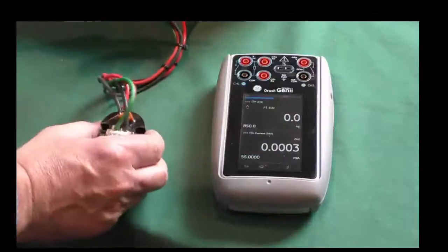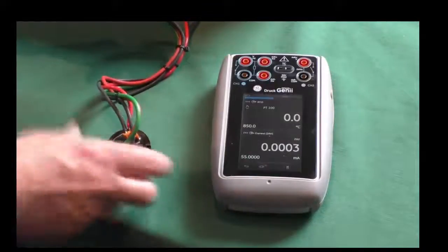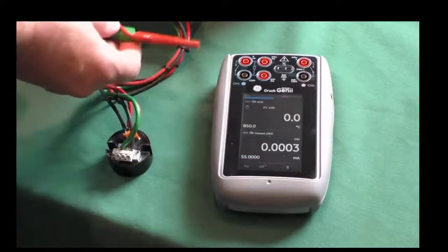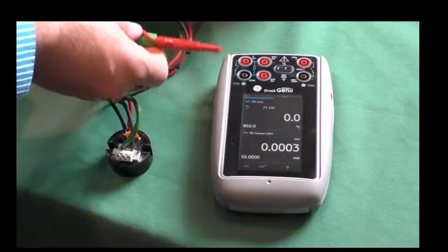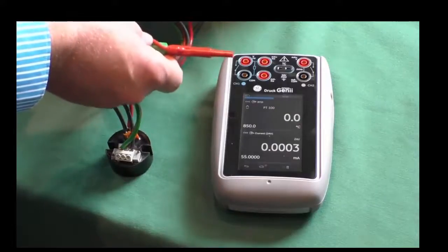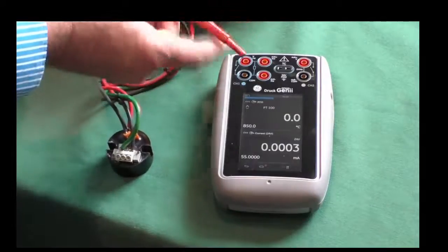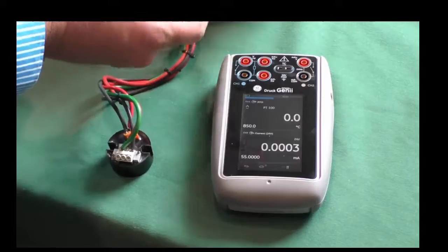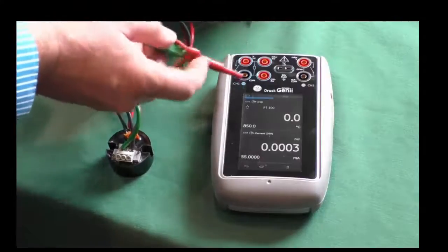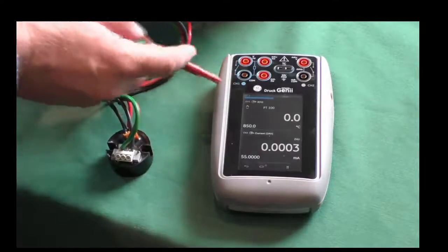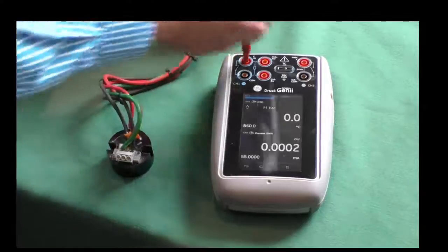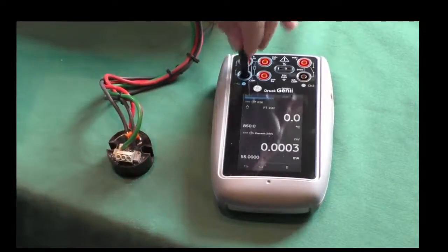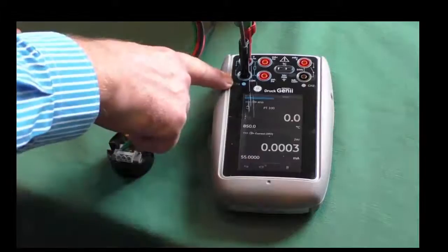So here I have a rather old RTD transmitter, it's a three-wire. When we're actually sourcing or simulating, we don't need to connect all three wires independently. So what I've done is I've joined the compensation wires together there. We make a simple connection on this side, so no matter which way around I do this, it's a resistance. So that's channel 1.